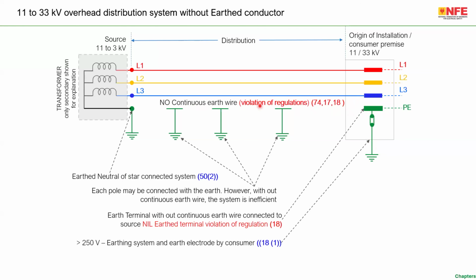So basically, if a continuous earth wire, that is, a continuous metallic fault return path, is missing for any application above 1 kV AC, it's a violation of the regulation. It's also a violation of the available standards so far. What I am saying is, all the available standards and regulations describe a system with a metallic fault return path for applications above 1 kV.